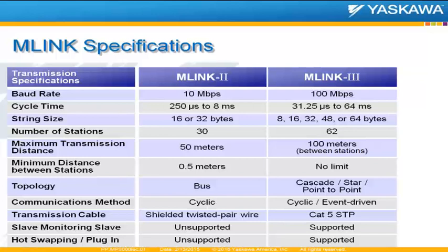One of the drawbacks in increasing this size is that now all the Servopack nodes are active nodes. They're no longer static. What that means is if the node is not powered, you lose everything downstream from that device. Under MECHATROLINK-II, it didn't matter if the node was powered or not. You could still see all the nodes as long as the cables were plugged in. But with MECHATROLINK-III, the device must be powered to see downstream devices.